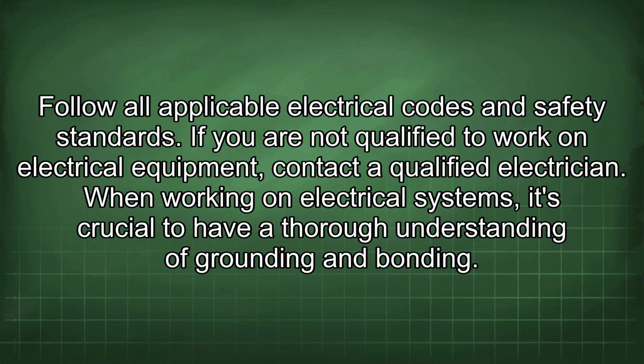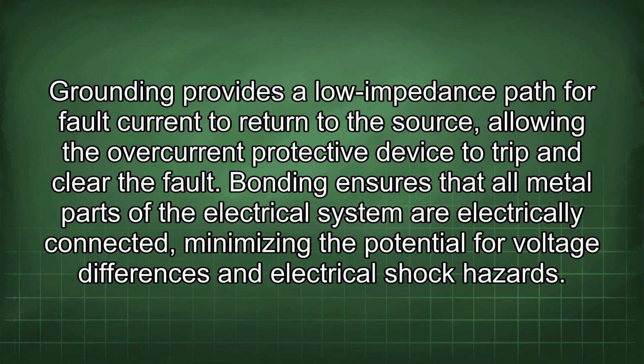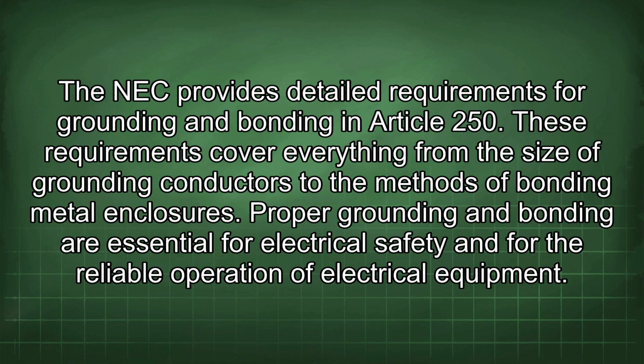When working on electrical systems, it's crucial to have a thorough understanding of grounding and bonding. Grounding provides a low impedance path for fault current to return to the source, allowing the overcurrent protective device to trip and clear the fault. Bonding ensures that all metal parts of the electrical system are electrically connected, minimizing the potential for voltage differences and electrical shock hazards. The NEC provides detailed requirements for grounding and bonding in Article 250.